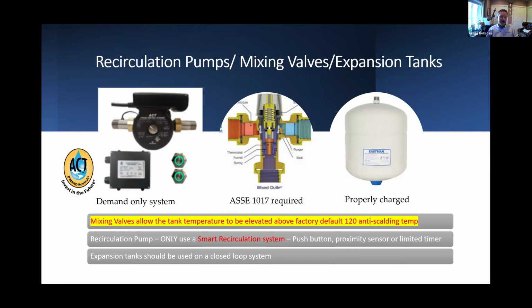Every manufacturer will approve that type, but they do that with a caution, because if you don't put one in that is a demand, then you're going to make this recirc line run all the time, which means the water heater is going to continually run and try to reheat that last 4 or 5 degrees, and it's never going to turn off, which means the manufacturer is then going to say, take that pump out and put one in that is smart. So keep that in mind as you look at these.